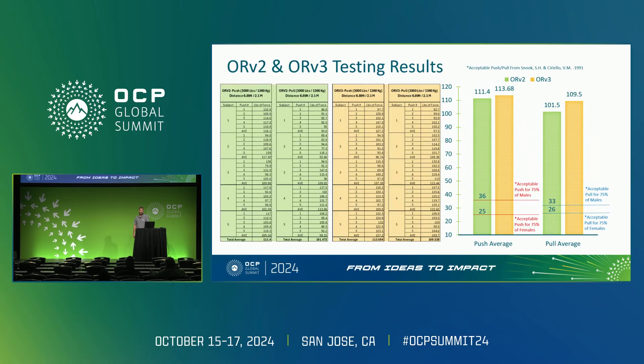For this study, we loaded each rack to 2,000 pounds to simulate a real-world scenario. We then set up a test in our customer experience center to measure the forces needed to push and pull these racks over a distance of approximately 6.8 feet, or 2.1 meters.